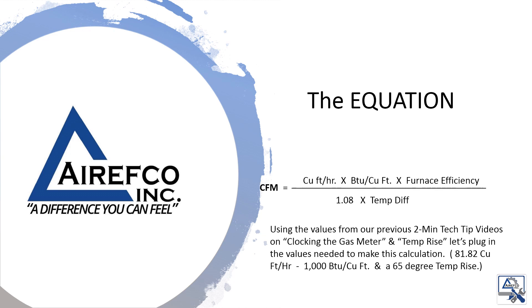Using the values from our previous two-minute tech tip videos on clocking the gas meter and temp rise, let's plug in the values needed to make this calculation. The values needed are 81.82 cubic feet per hour, 1,000 BTUs per cubic feet, and a 65 degree temperature rise.